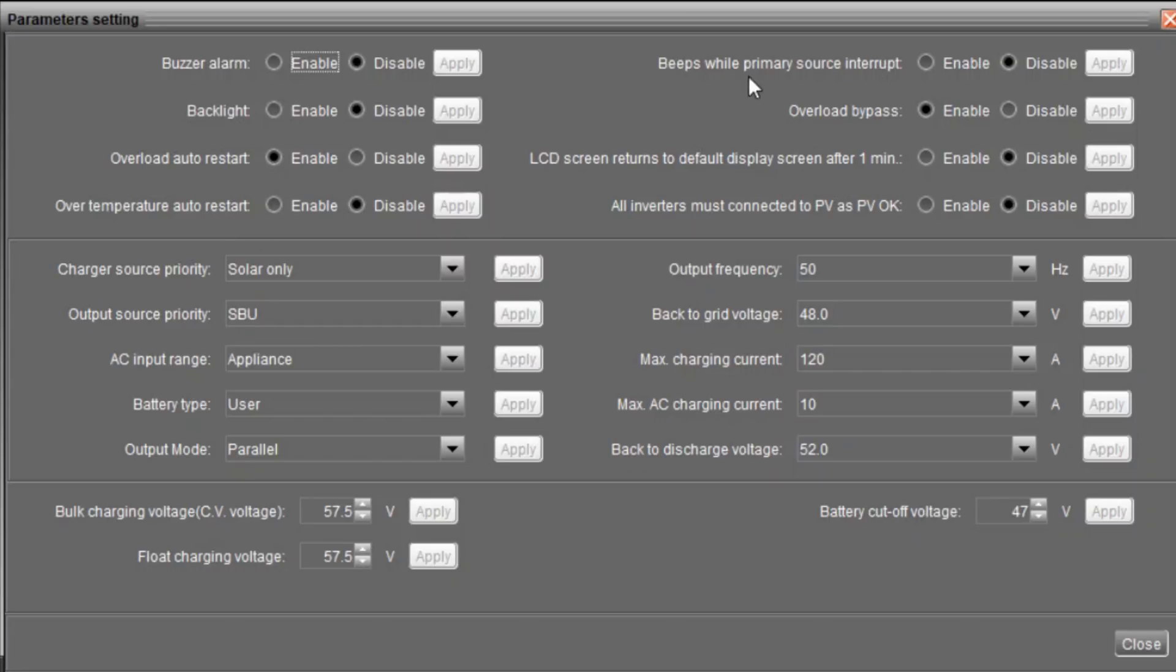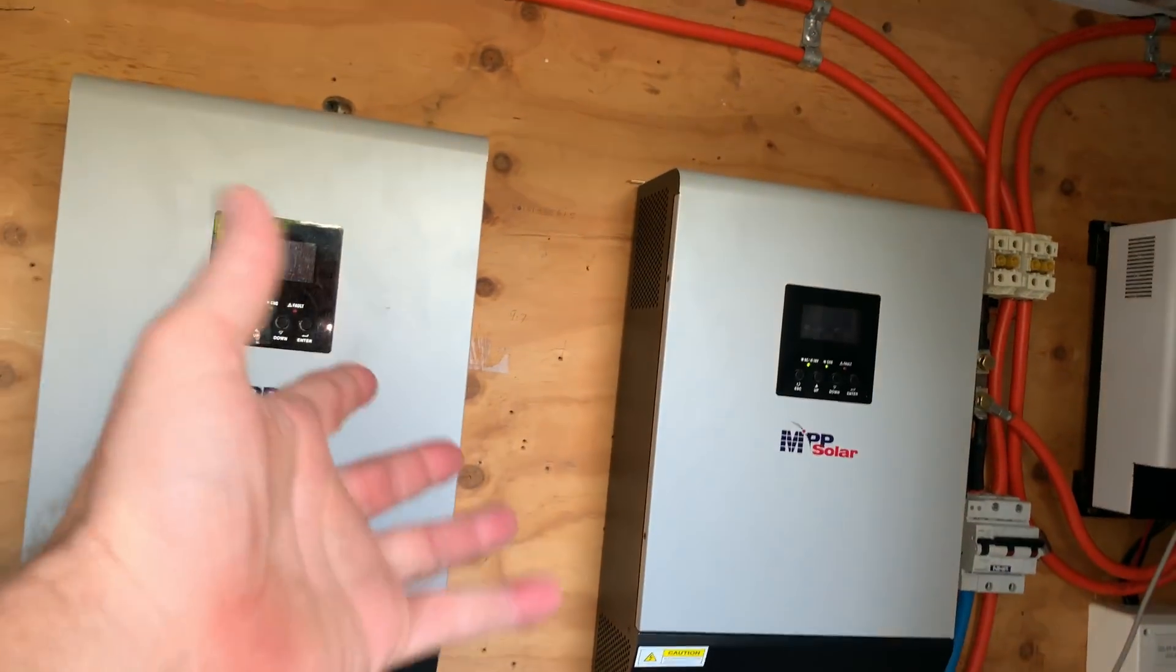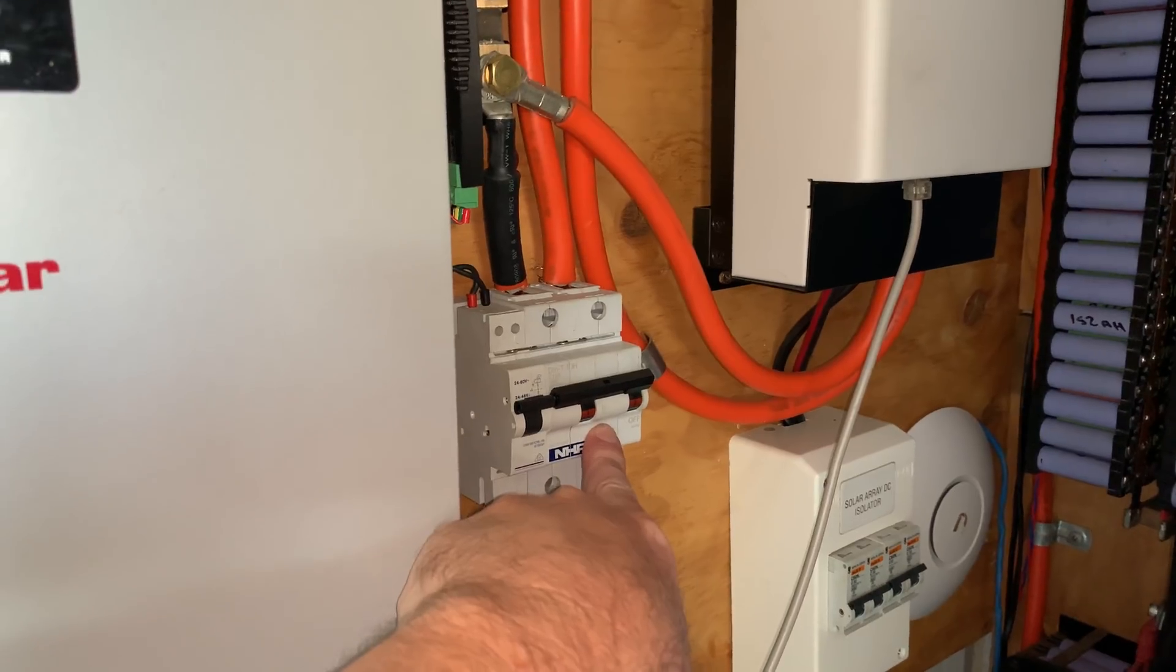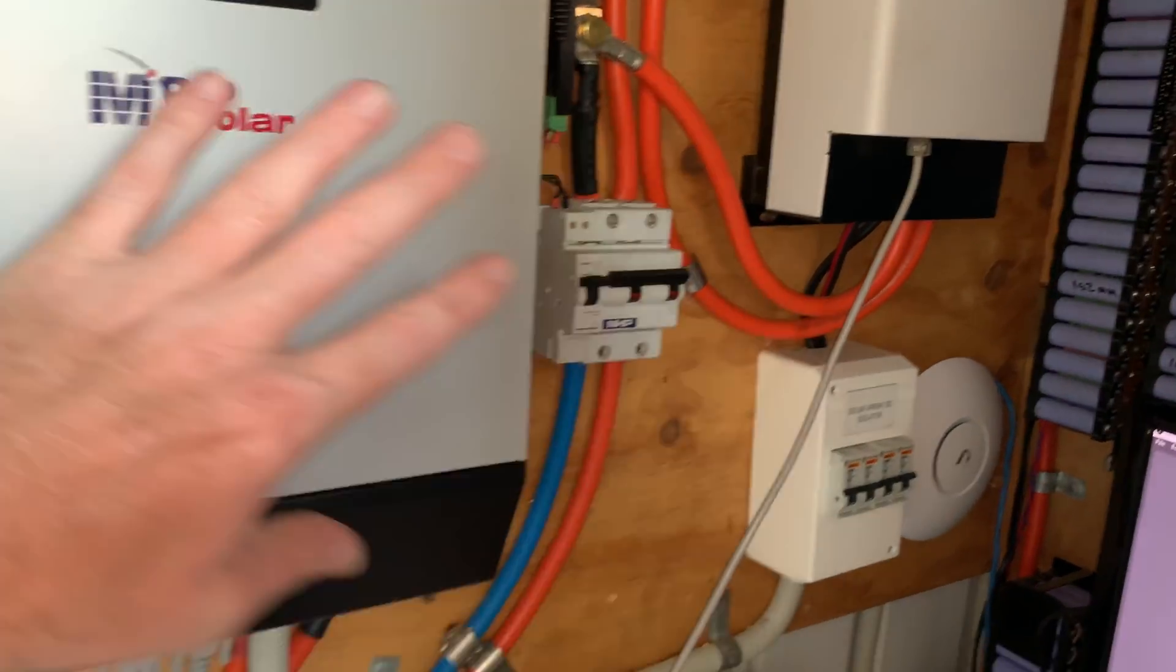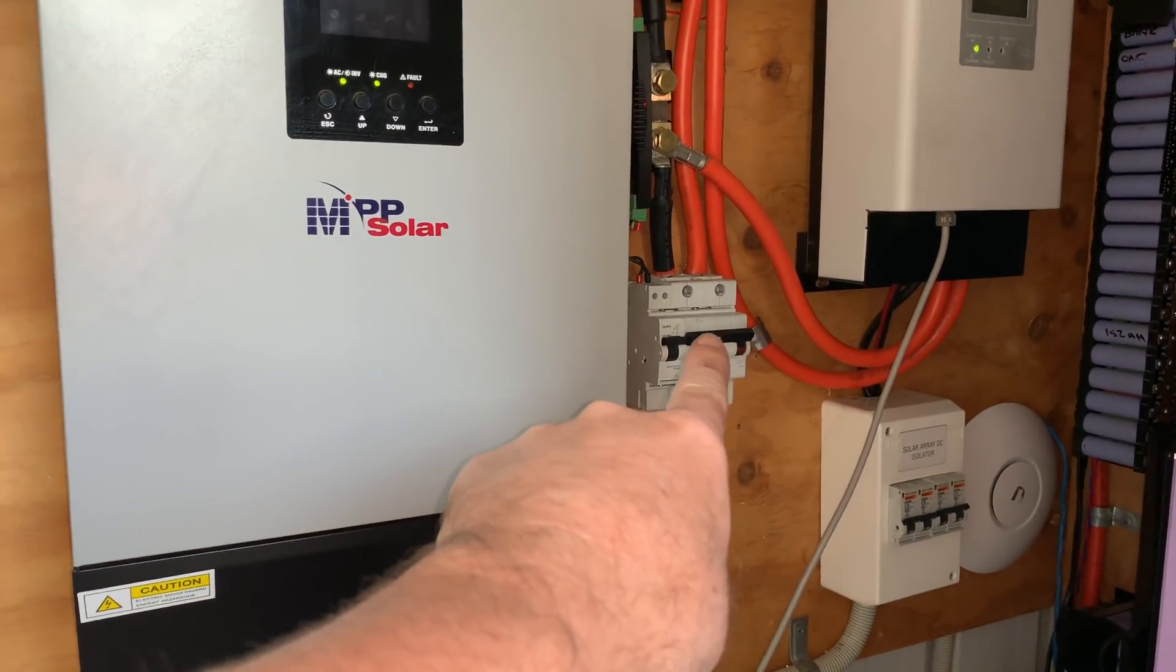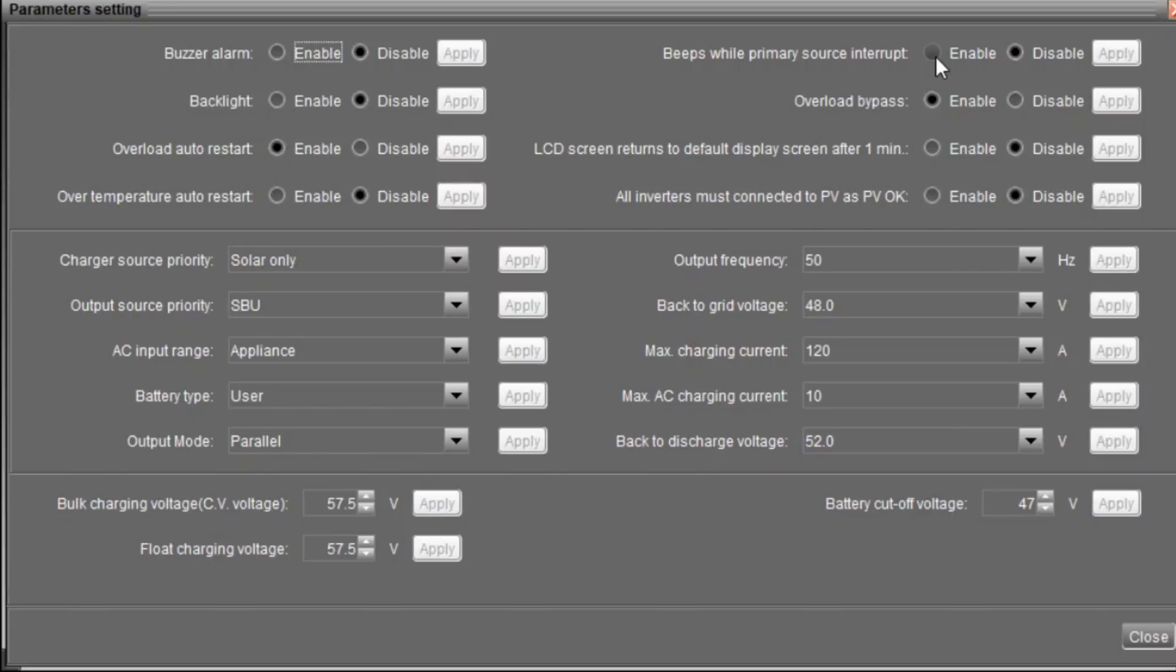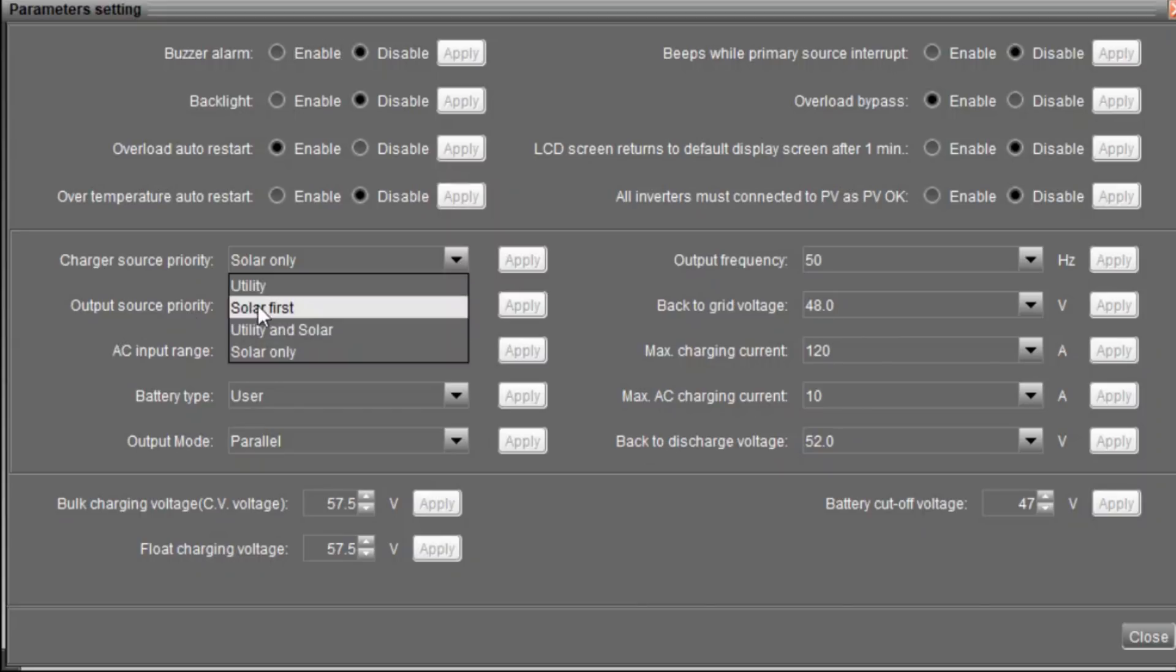Over temperature auto restart is set to disable because if it over temperatures, I do not want the inverter to turn back on again—I want to investigate. Beeps while primary source interrupt enabled—disabled because that's a really annoying beep. If anybody knows these MPP Solar units or any PIP type unit, as soon as you remove the battery, that's the primary source. So even if you've got them turned off and isolated and whatever else, they've got that on there—they're drawing I know 30 to 60 watts each.